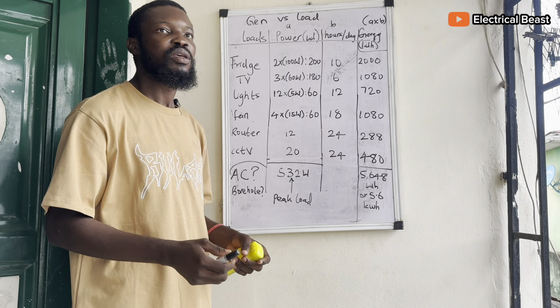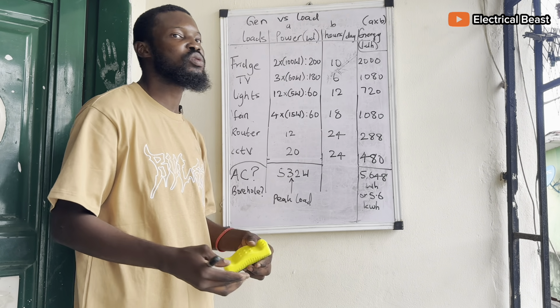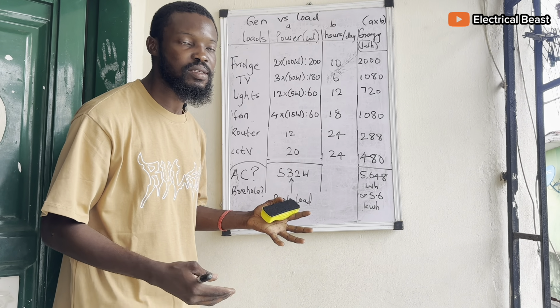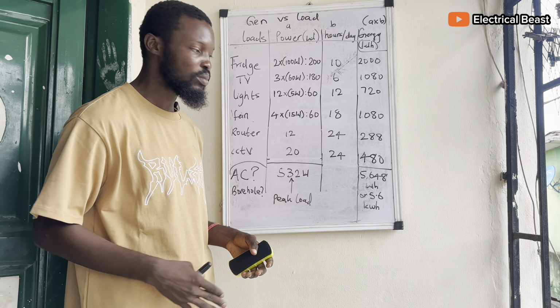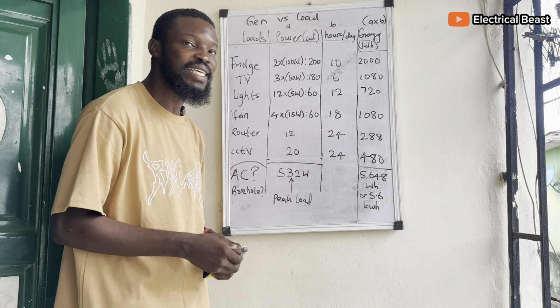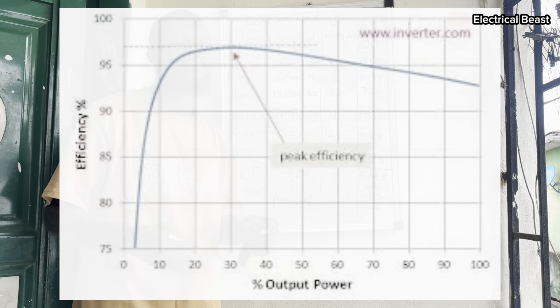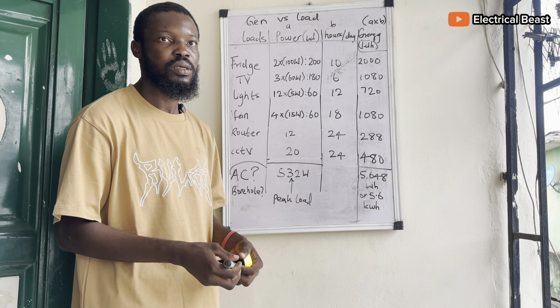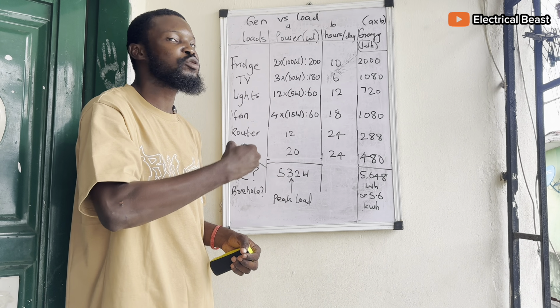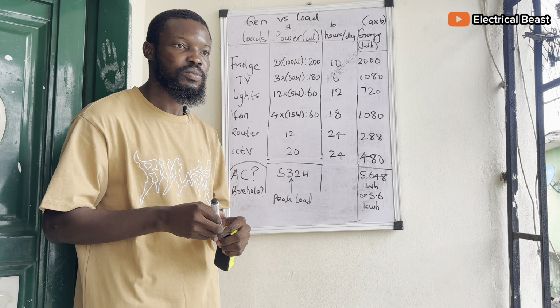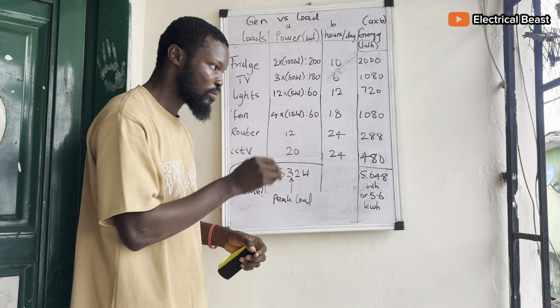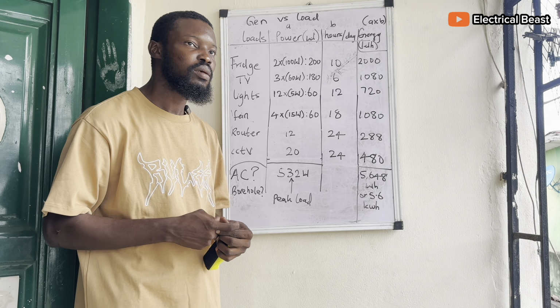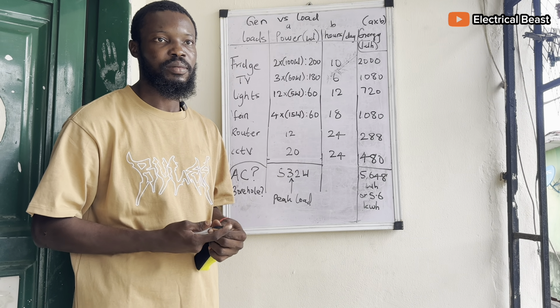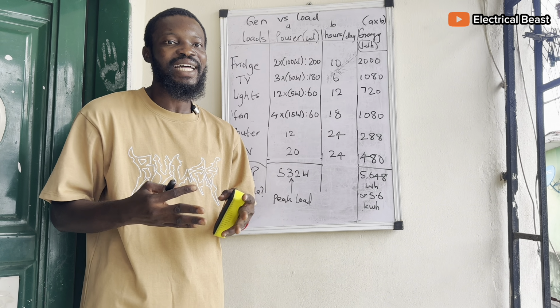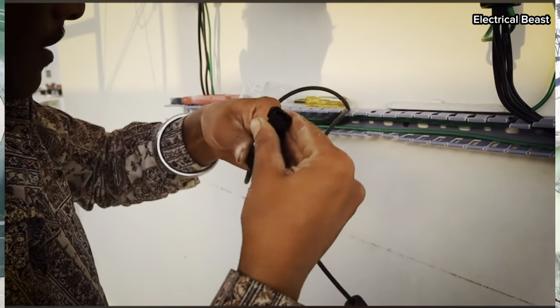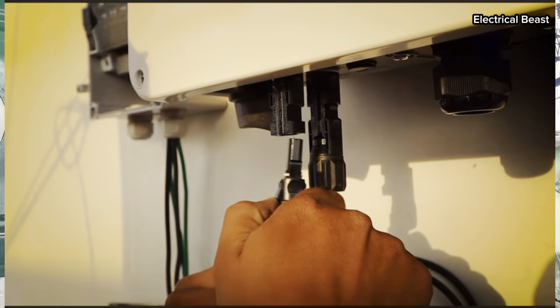And so, even when you want to consider future addition of load, you may want to add a microwave later, you might decide to buy 3 extra fans. So you need to create room for the future load that you will add, and also consider the inverter's efficiency. Most times these inverters have an efficiency value of 80%, 90%, 70%. That's actually the reason why you have to estimate the power of your inverter. So when you put all those into consideration, these are peak load, but let's make this 3.5 kVA, or let's just make it 5 kVA. If you want to add more load, it depends on the kind of load you want to add. If you want to add just maybe an extra refrigerator, 2 fans, 3.5 kVA.